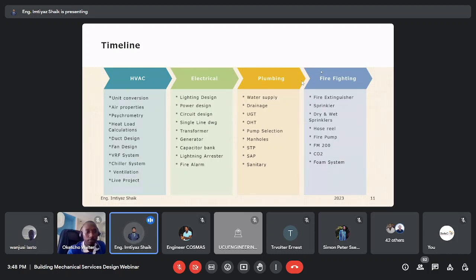And we have heat load calculations - we can call it heat or cool load calculation, both sound similar. Here we cannot just say that for one building you put a 1 ton AC or 2 ton AC - you can't decide just by looking at the building. You need to properly calculate how you define whether 1 ton, 2 ton, or 50 ton AC is required. So we go point by point with calculations in this.